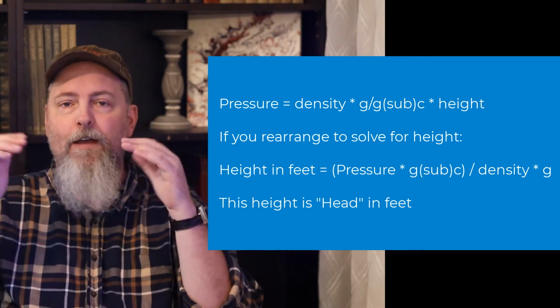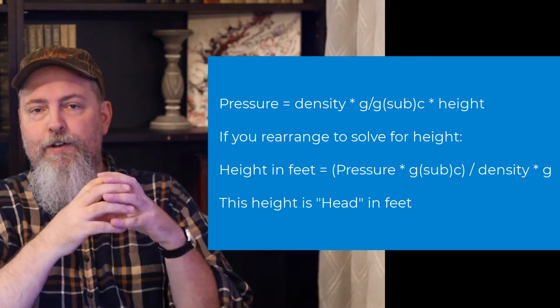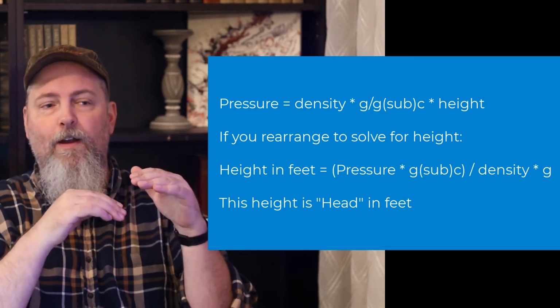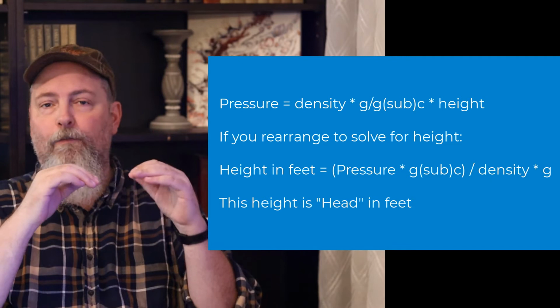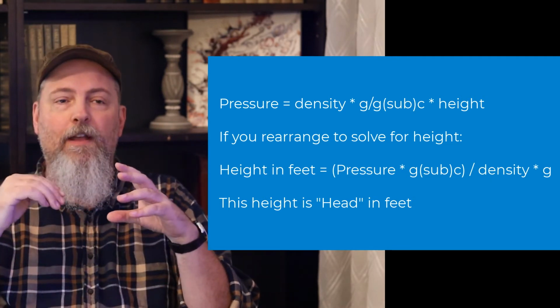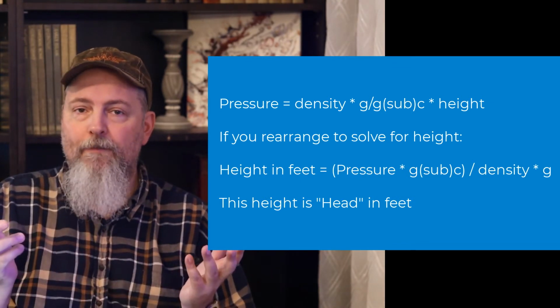What's going to be different between pumping ketchup and pumping distilled spirits or water, right? Well, it comes down to the density. The densities of each of those change the pressure, discharge pressure. So when you think about your units, a feet of head, all you have is feet. And when you think about pressure, pounds force per inches squared, and you take out the gravitational constant, so you work from pounds force backwards to pounds mass, and then you take out the density of the fluid, the only unit you're left with is feet.